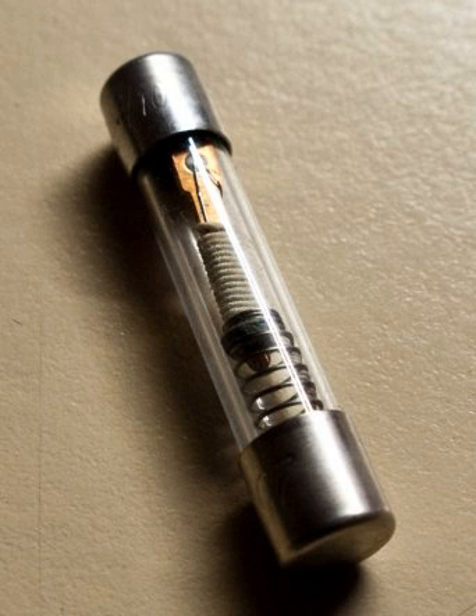Fuses for small, low voltage, usually residential, wiring systems are commonly rated, in North American practice, to interrupt 10,000 amperes. Fuses for commercial or industrial power systems must have higher interrupting ratings, with some low voltage current limiting high interrupting fuses rated for 300,000 amperes. Fuses for high voltage equipment, up to 115,000 volts, are rated by the total apparent power megavolt amperes, MVA, of the fault level on the circuit.